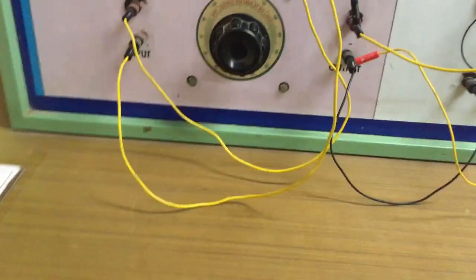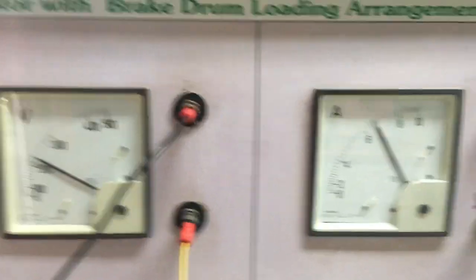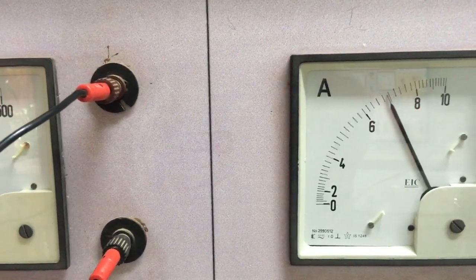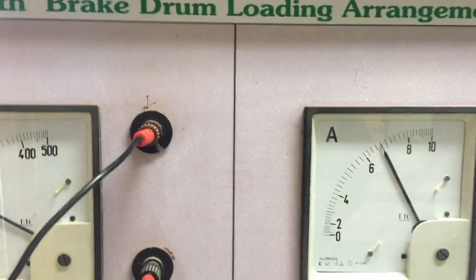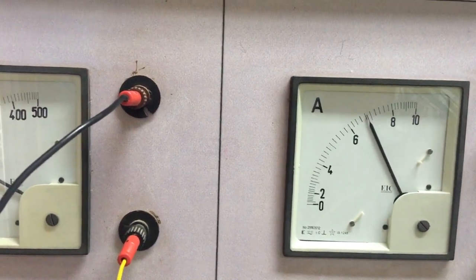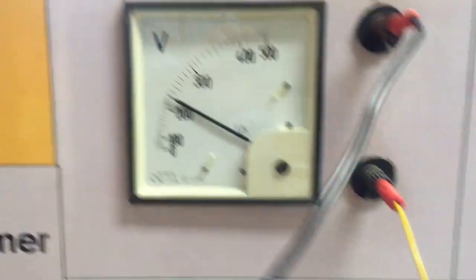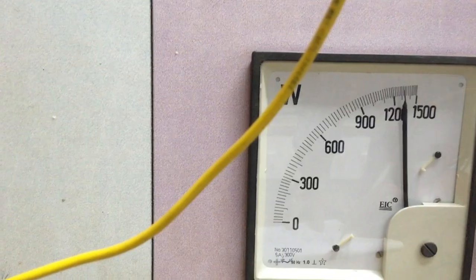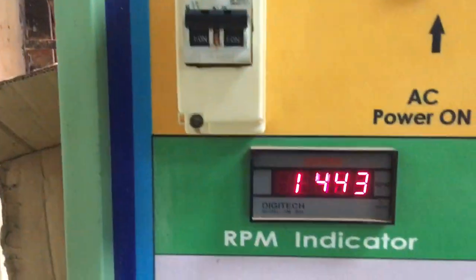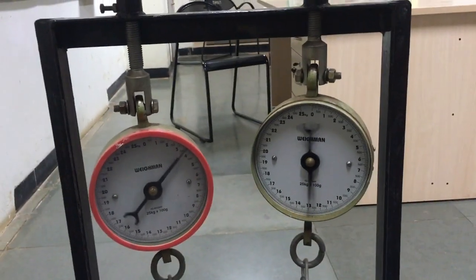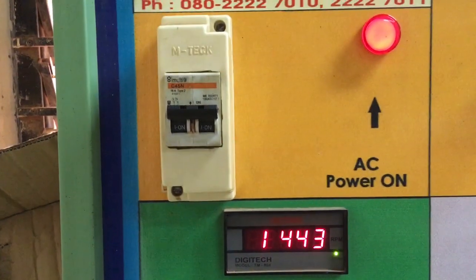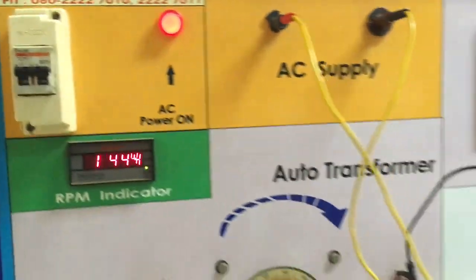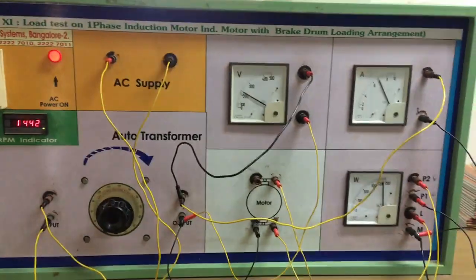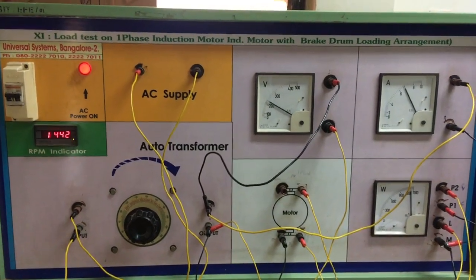The last reading I will take at 6.8. 6.7 is the rated current, but 6.8 will do. No issues, because I can read 6.8 conveniently on the meter than 6.7. Power is 1300. Spring balances are 13.4, 2 and 3.5. Speed is 1444. Now the motor has reached its rated current. Further I cannot vary the load because the motor will become overloaded. I will stop loading it.